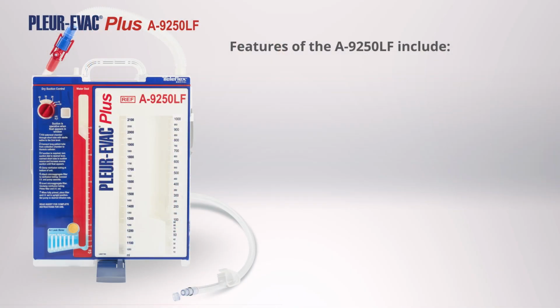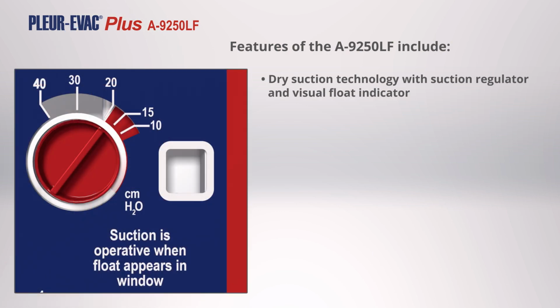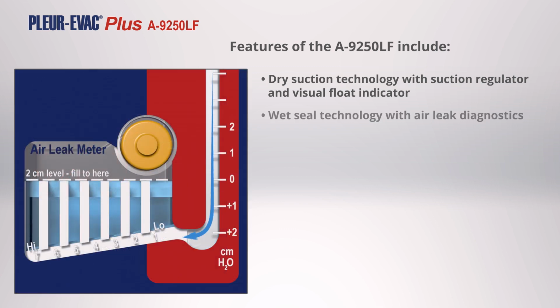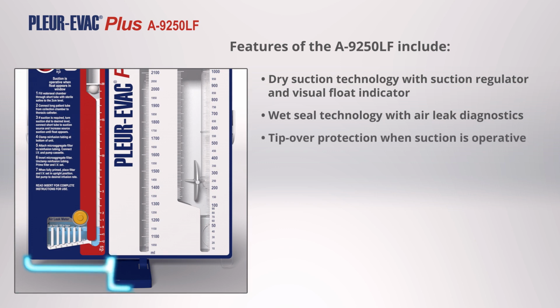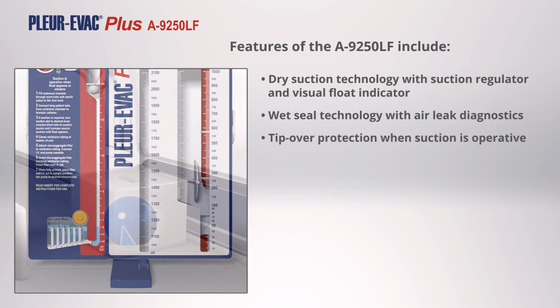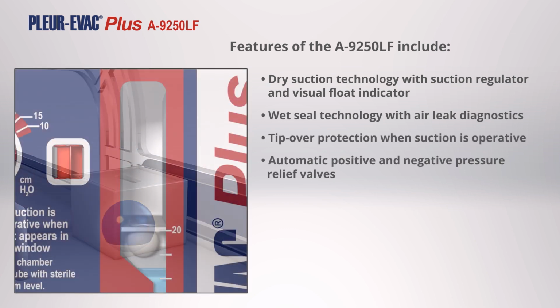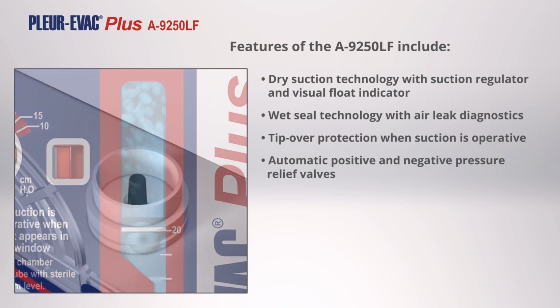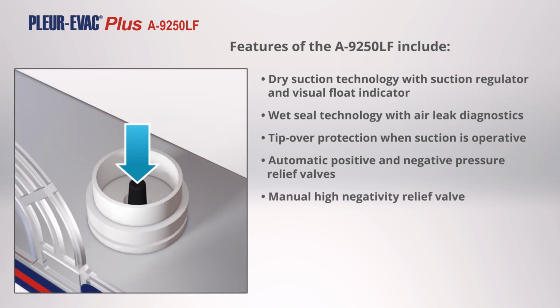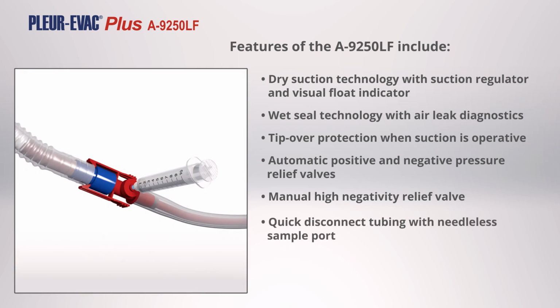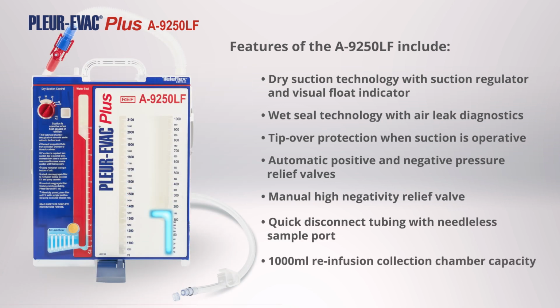Summarized features of the A9250LF include dry suction technology with suction regulator and visual float indicator, wet seal technology with air leak diagnostics, tip-over protection when suction is operative, automatic positive and negative pressure relief valves, manual high negativity relief valve, quick disconnect tubing with needleless sample port, and 1,000 milliliter reinfusion collection chamber capacity.